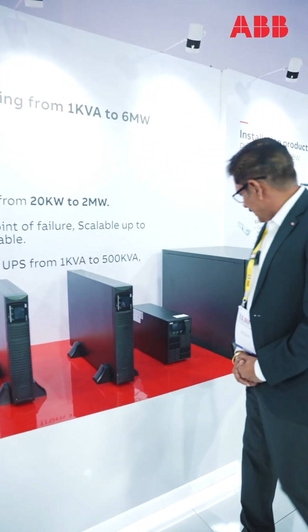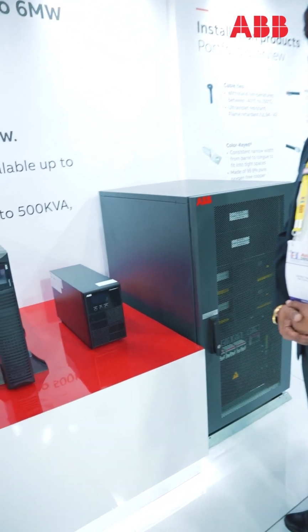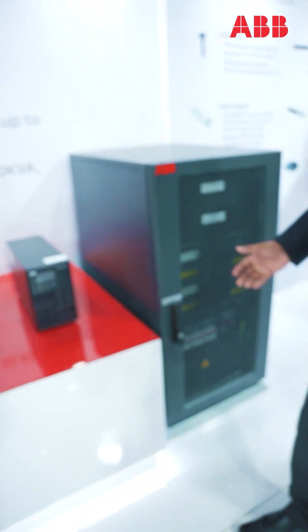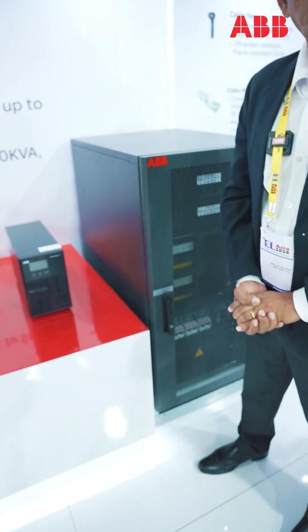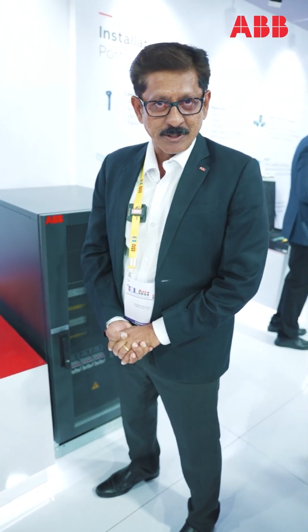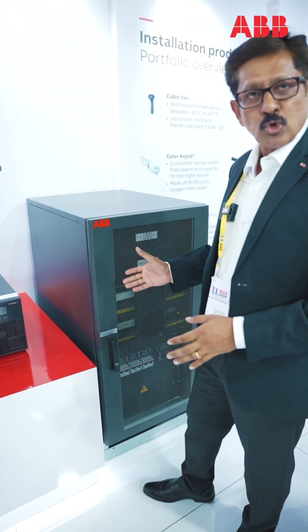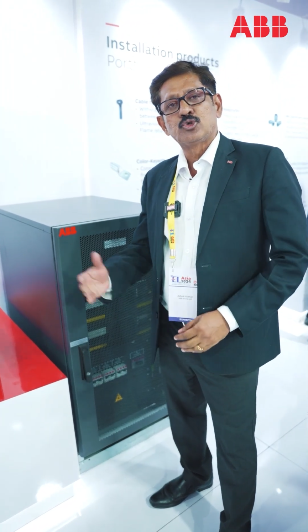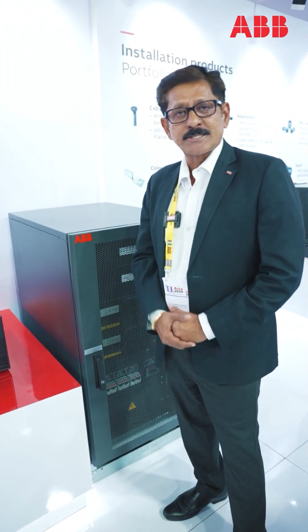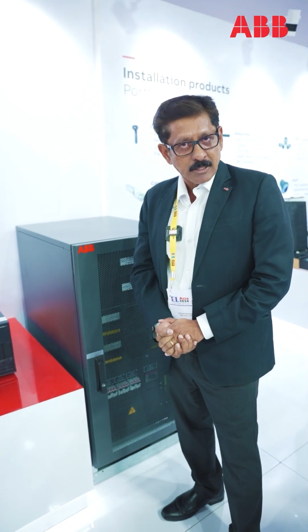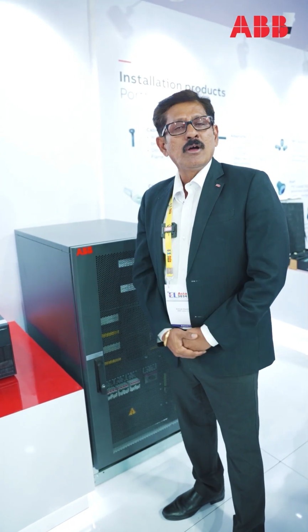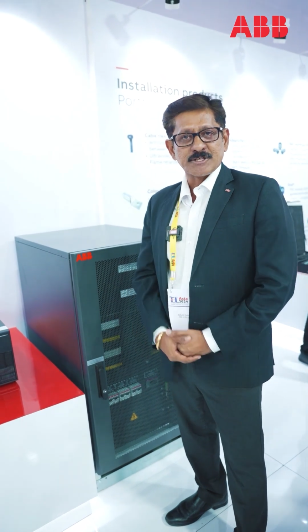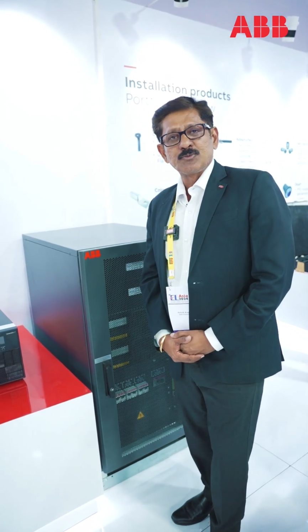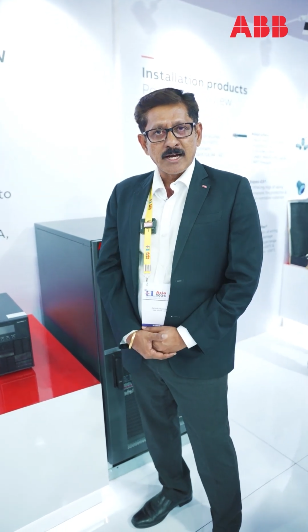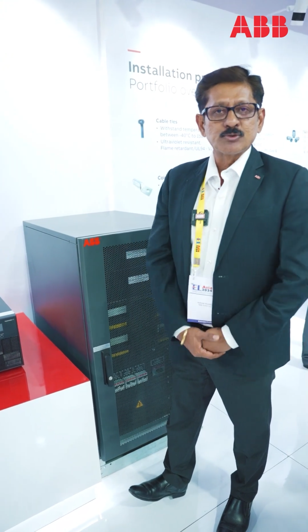And apart from that, we have modular UPS systems, which is the DPA modular UPS. In DPA modular UPS, we can give solutions from 20 kilowatt to 6 megawatt. The 20 kilowatt range goes up to 200 kilowatt, with 40 kilowatt modules, and we can give solutions up to 200 kilowatt. 200 can be paralleled to almost 1.2 megawatt. Then the Megaflex UPS range starts with 250 kilowatt modular UPS, and 250 kilowatt is scalable up to 2 megawatt. From 2 megawatt, again, we can do a solution up to 6 megawatt.